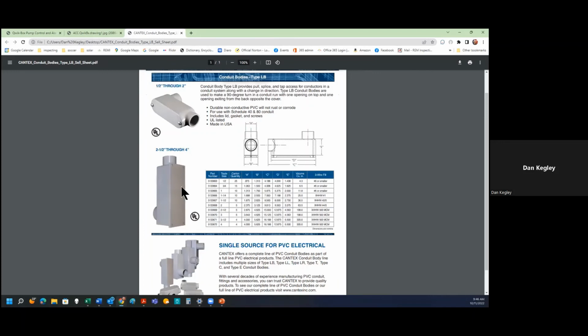But in the LB boxes, if you do use LBs, certainly you can use the wires if you have your box inside your actual tank itself. So if you transition from outside to inside the tank, and then you have your junction box inside the tank, which is allowed, you can certainly use this as a transition coming out of the ground and in. That's not a problem.